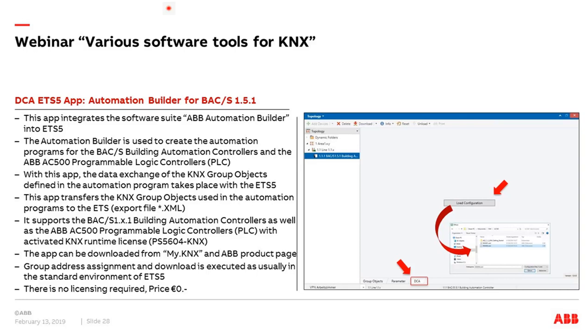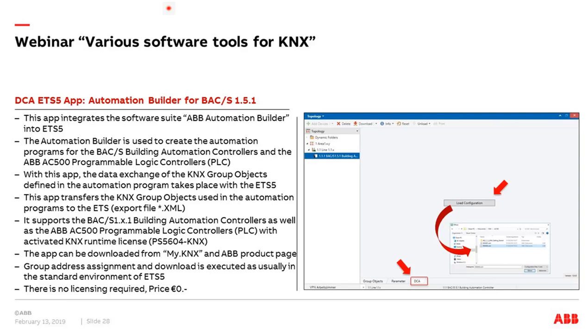So with the building automation controller DCA, the process is simple: export XML from automation builder, import in ETS via the DCA, assign group addresses, download — and then it connects to your logic inside the building automation controller. You can see that DCA usage can be totally different depending on the product. More details are available in dedicated webinars for both the application controller and building automation controller done last year.